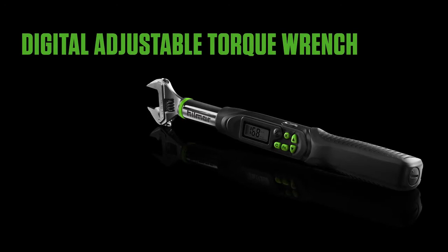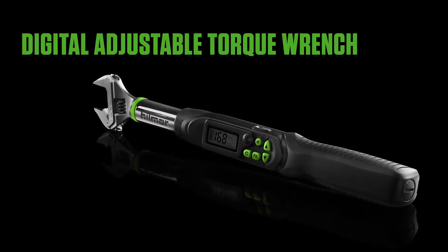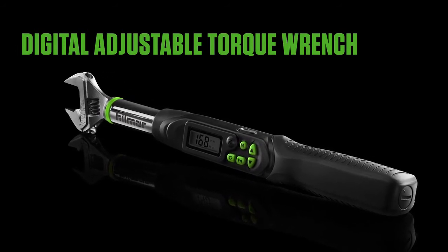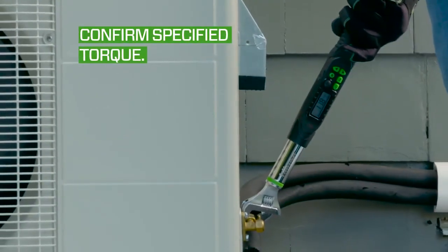When you're tightening flare nuts on mini-splits, achieving the perfect torque is critical for preventing refrigerant leaks. Hilmor's digital adjustable torque wrench makes setting torque as easy as a push of a button. Start by confirming the torque specified by the mini-split unit manufacturer.